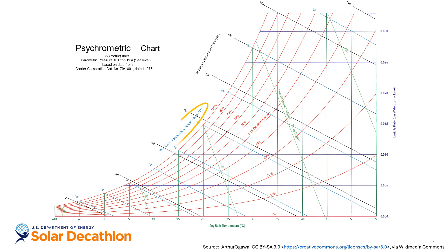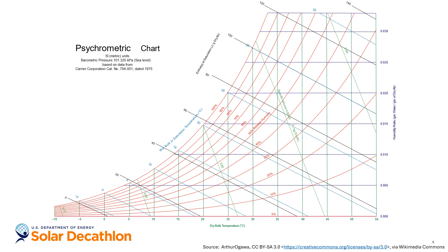The next term is the wet bulb temperature, shown as diagonal blue lines. Think of wet bulb temperature as an expression of how cool the air can become through evaporative cooling. It's determined by wrapping a thermometer's bulb in a wet cloth and measuring the temperature as water evaporates from the cloth. When water evaporates, it absorbs heat energy from the surrounding air, causing a cooling effect. When the difference between dry bulb and wet bulb temperature is large, it means water is evaporating quickly and the surrounding air is drier — lower humidity.